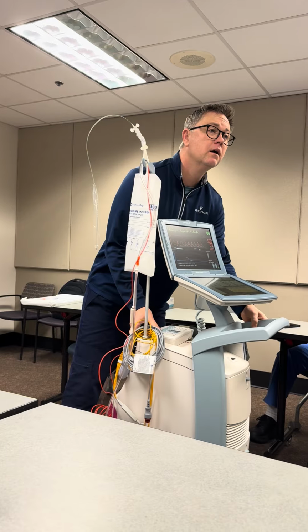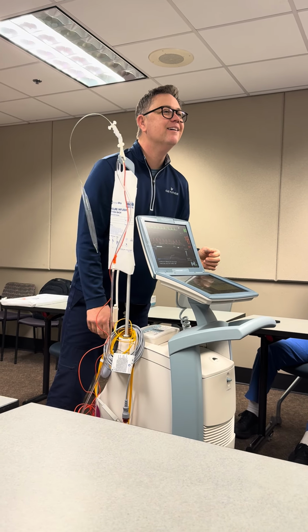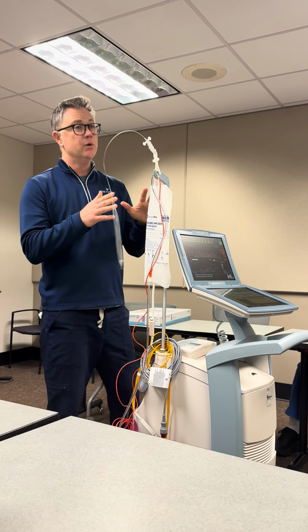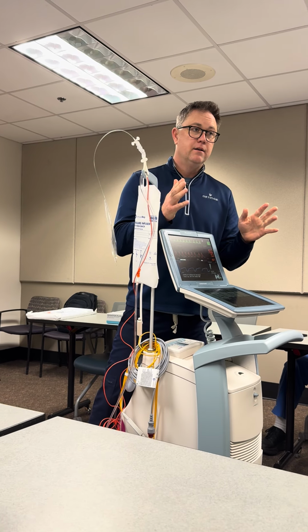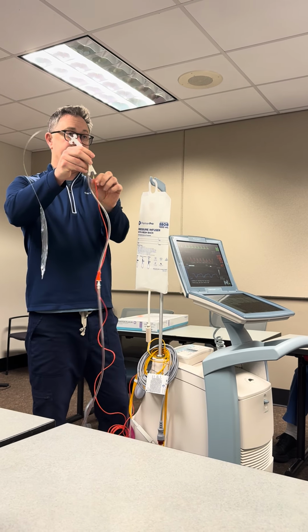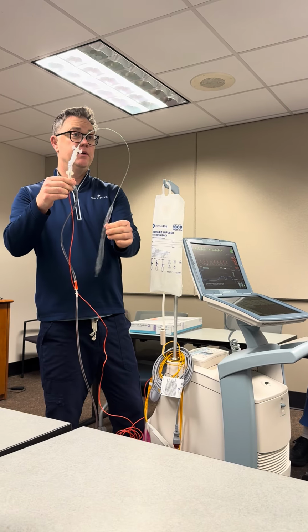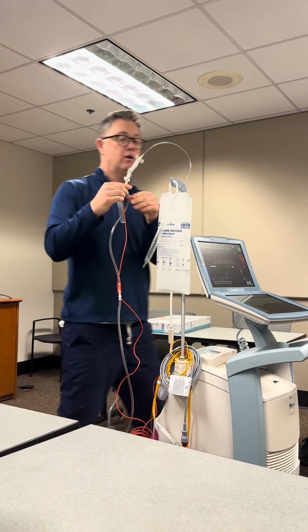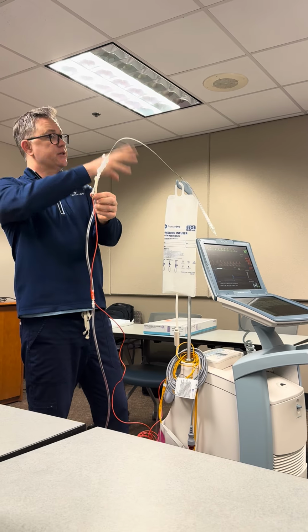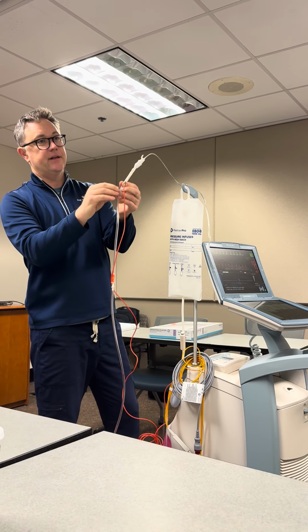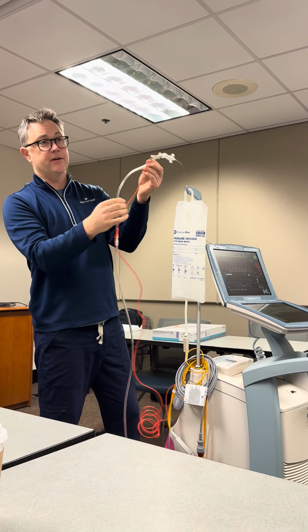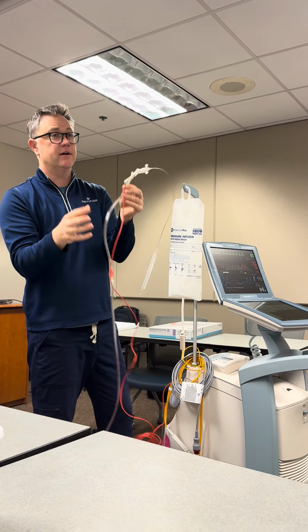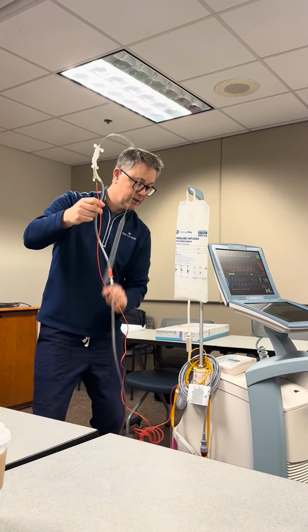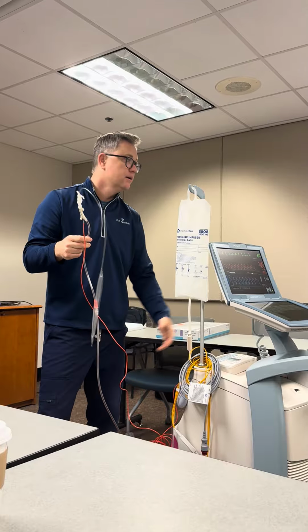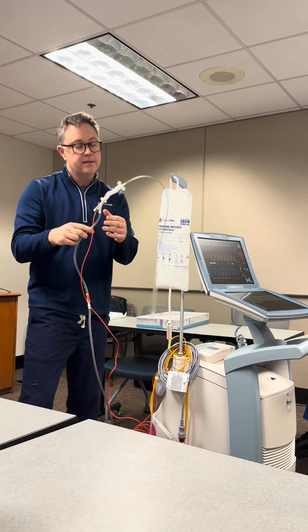Yeah. So why would I clamp it there? Why wouldn't I just unplug it? Yeah, this is a newer thing that we're asking people to do. The problem that we've had is that newer nurses don't realize that they've got a ruptured balloon and they continue to hit start. When you hit start, the balloon tries to start up again, and you're inflating and deflating and sucking blood in, and they're not checking their helium line and noticing the blood. What we've had happen is they've sucked blood all the way back to the machine, to the point where blood has gotten into the machine. So that's the new protocol.